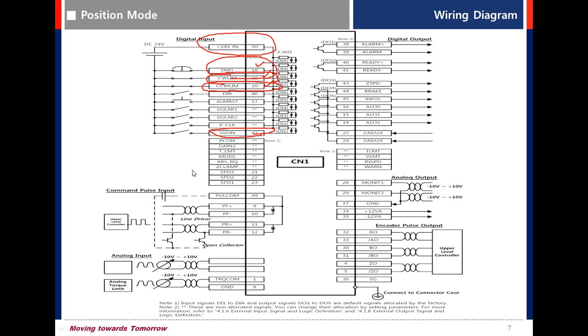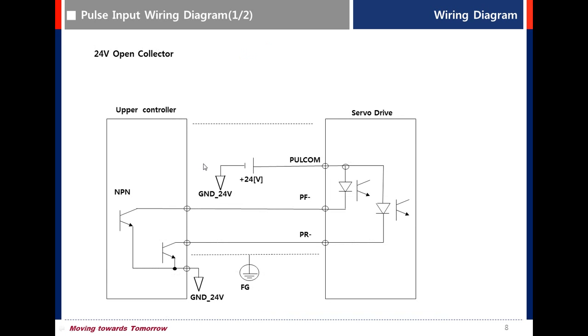To wire command pulse input from the upper controller, there are two types: line drive type and open collector type. For 24V open collector, connect PULCOM, PF minus, and PR minus.